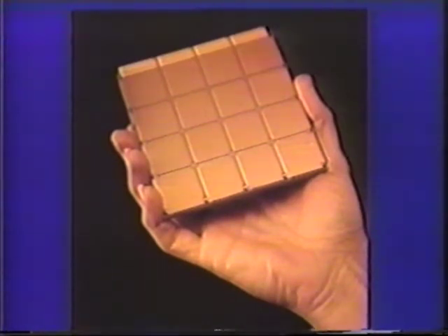The liquid flows right through these modules, not perpendicular, but longitudinally. Total path for the liquid is the 4 inches you see, because these modules, 200 of which make a 16 processor machine, are arranged in a circle around the top of the tank you saw. The liquid flows vertically right up through the module, flows around the die, and goes back down a supporting pipe between the octants in the machine. So total fluid travel is 4 inches, and velocity is 10 inches per second.